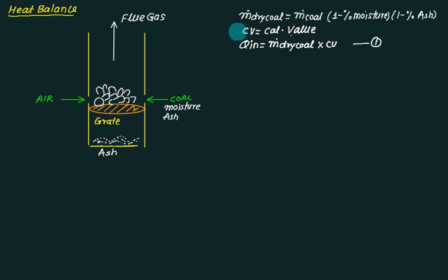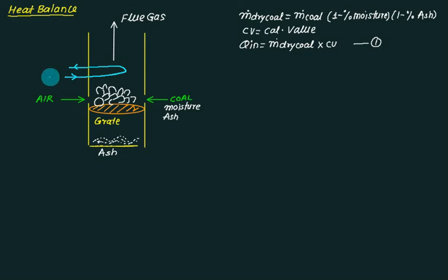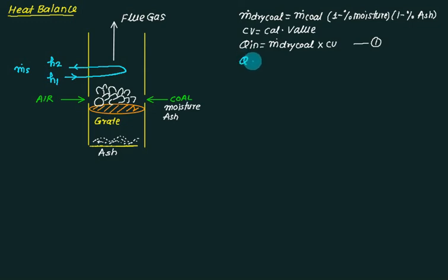In the heat balance, we find how this heat has been utilized for various purposes. First, some heat is carried by steam. h1 is the enthalpy at inlet, h2 is the enthalpy at outlet, and m_dot_s is the mass of steam. Heat gained by steam equals mass of steam multiplied by (h2 minus h1).